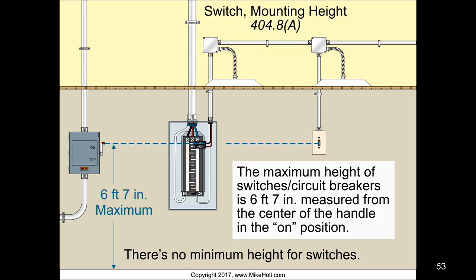Switch location. 404.8(A) says the maximum height for switches or circuit breakers used as switches is 6 feet 7 inches, measured from the center of the handle in the on position. So the maximum height is right there. Now there's no minimum height, just the maximum height of the switches.